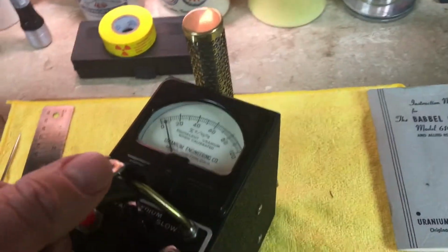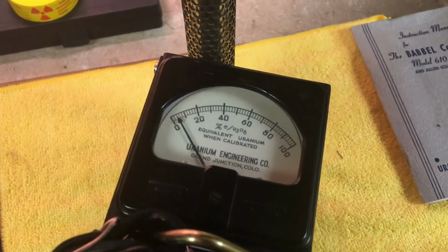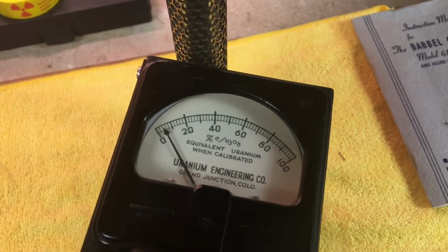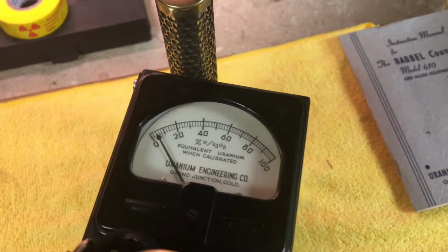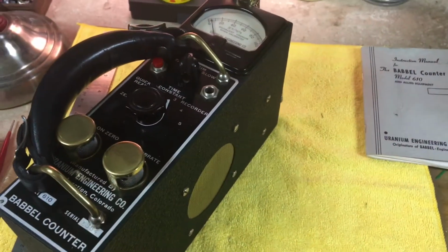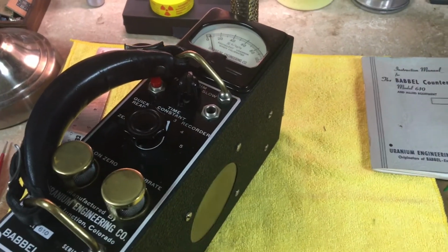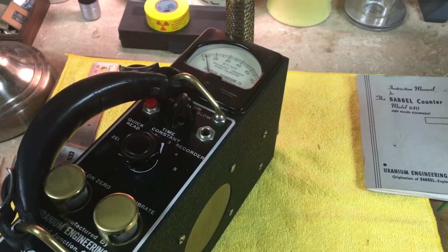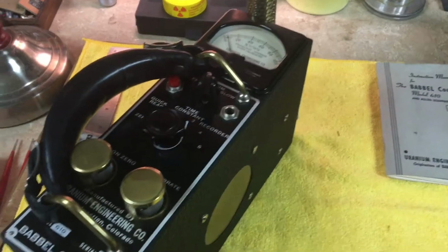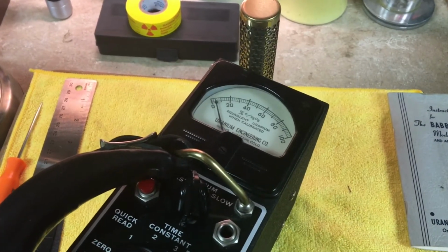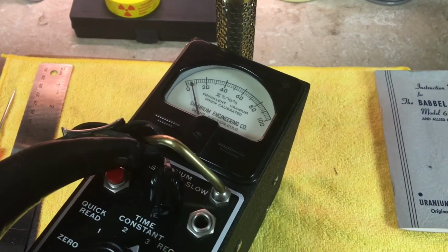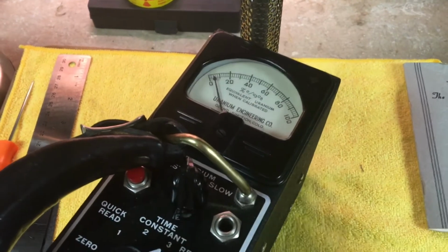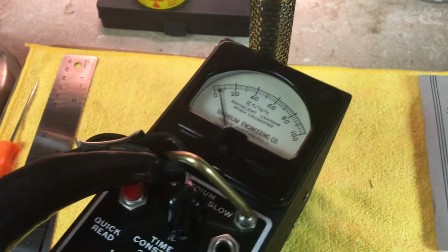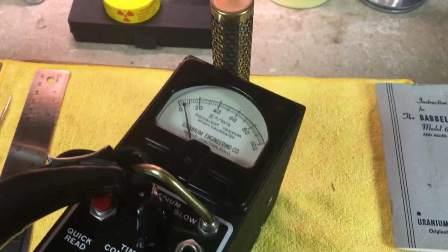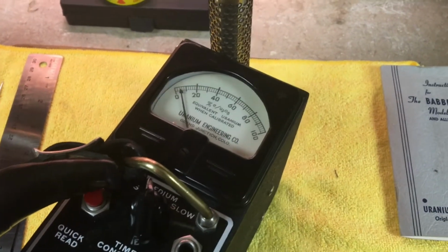All right, so this does not operate in counts per minute. This thing is specifically for equivalent uranium when calibrated. So you can see here it's got a percentage of U3O8. Now, how this is done is you would get a calibrated sample to calibrate this thing with, basically something that they already know has a 50, 75, or 100% percentage of uranium. Then by using the calibration controls here, you would calibrate this thing to have a 100% or 50% reading based upon the sample that you already know is 50% uranium or 100% uranium, whatever the percentage was that you're going to use. Then when you go into the mine to look for the uranium, you'd be able to get a rough estimate of the percentage of what you're looking for.